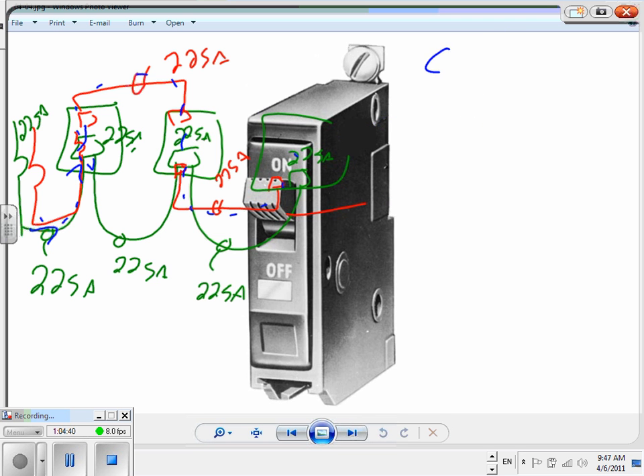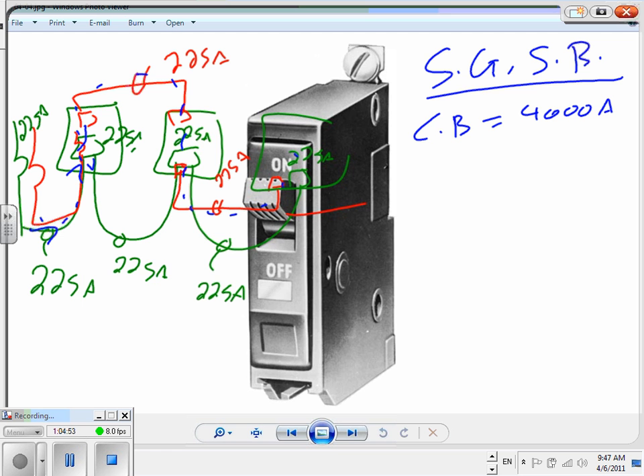Switchgear. If you have a switchgear or switchboard, this is mainly for switchgear, switchboard. Let me give you an example. Here is a circuit breaker, and the circuit breaker is 4,000 amp. They have three sizes for the circuit breaker. It's not enough, Spencer, to say I have a 4,000 amp circuit breaker. That's meaningless. You're going to find each one of them has three sizes. Number one is frame size, 4,000.